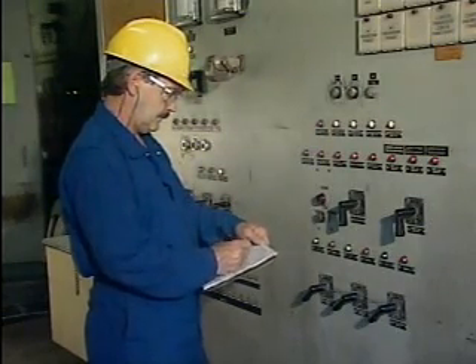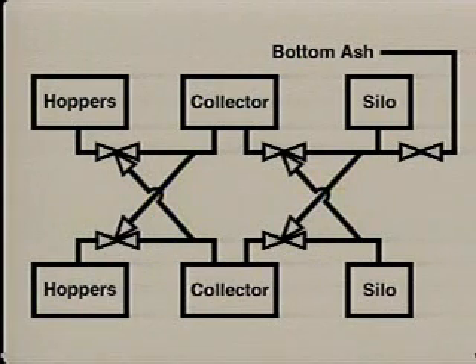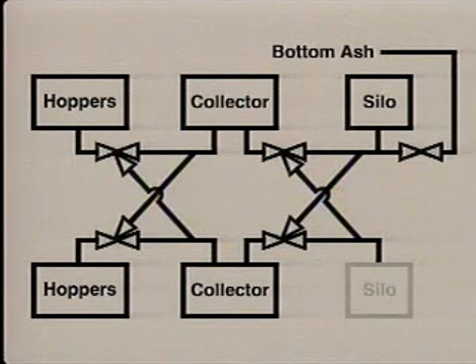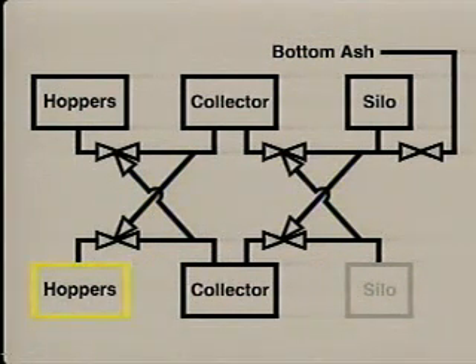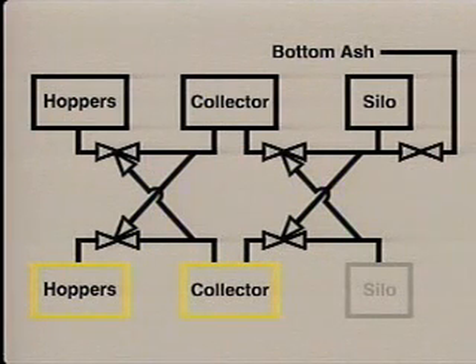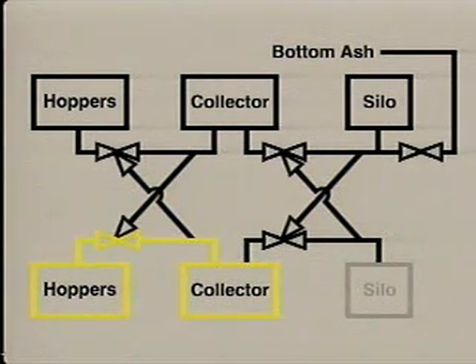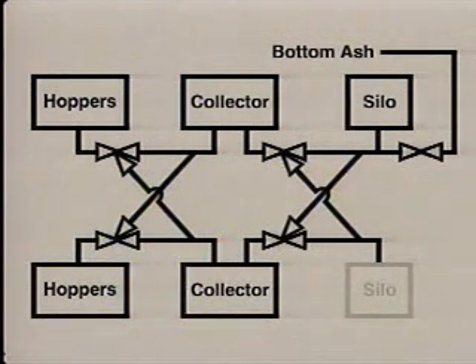We can use the illustration that we looked at earlier to get a better idea of what the electrician has learned from the control panel indicators. Because the B system was operating normally before the B silo had to be taken out of service, the electrician can eliminate the B system hoppers, the B collector, and the flow path between the two as possible causes of this problem. He can also eliminate the vacuum pump and the pressure blower for the B system.